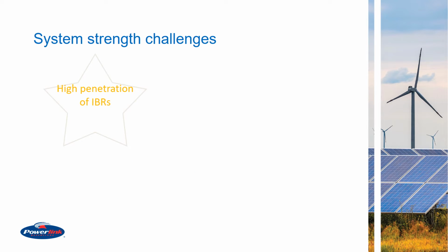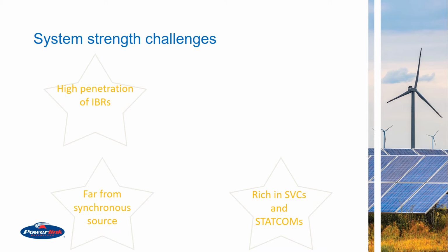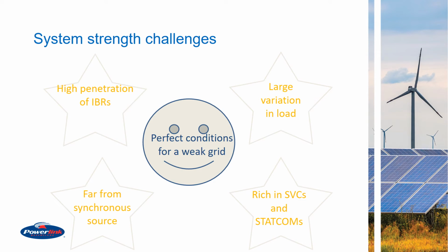So, in terms of system strength challenges, what we have is high penetration of inverter-based resources. We are very rich in SVC and STATCOMs, and those IBRs are far from synchronous sources, with large variation in load. And this basically makes a condition as if all the stars are aligning for a perfect system strength challenge. And it really makes a perfect condition for a weak grid.